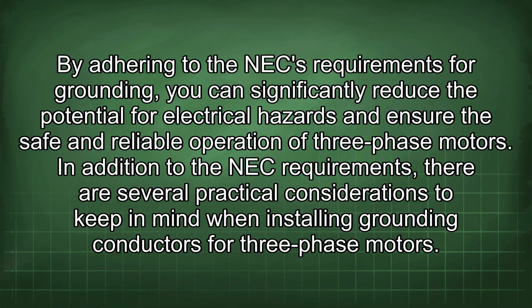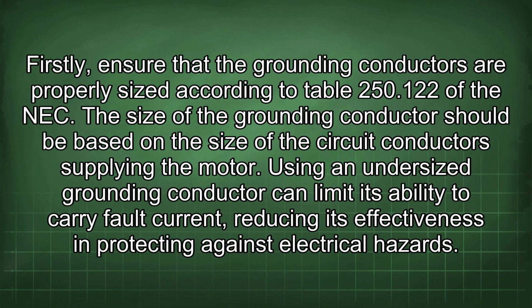In addition to the NEC requirements, there are several practical considerations to keep in mind when installing grounding conductors for three-phase motors. Firstly, ensure that the grounding conductors are properly sized according to Table 250.122 of the NEC. The size of the grounding conductor should be based on the size of the circuit conductors supplying the motor. Using an undersized grounding conductor can limit its ability to carry fault current, reducing its effectiveness in protecting against electrical hazards.